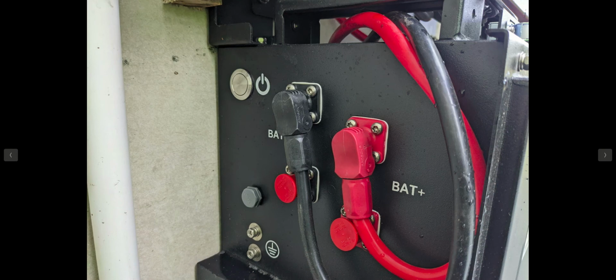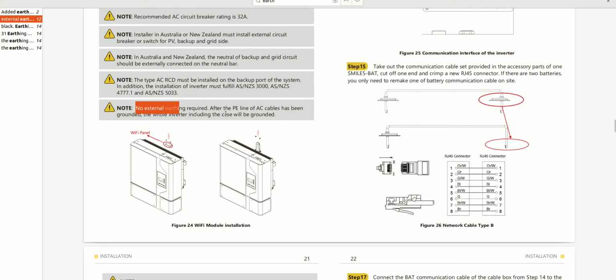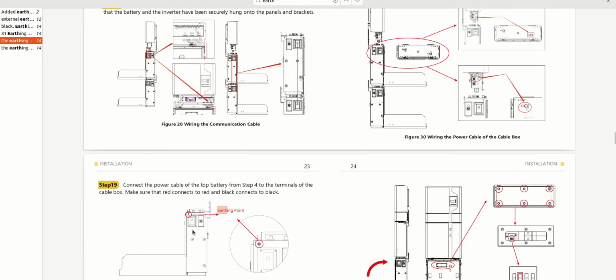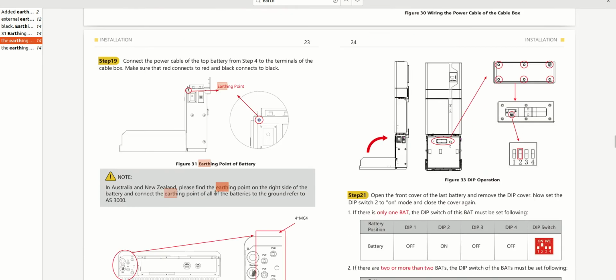So well, let's look what the instructions say. No external earthing required. After the protective earth line of the AC cables has been grounded, the whole inverter, including the case, will be grounded. So the whole case is going to be grounded. That's what it says there. And the inspector was happy with that. Here it says, though, later on that there's an earthing point that has to, of all of the batteries. So it's kind of like hinting that we're talking about linking batteries together.